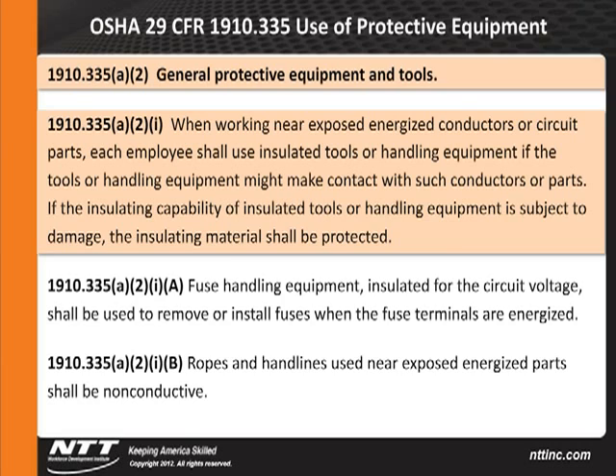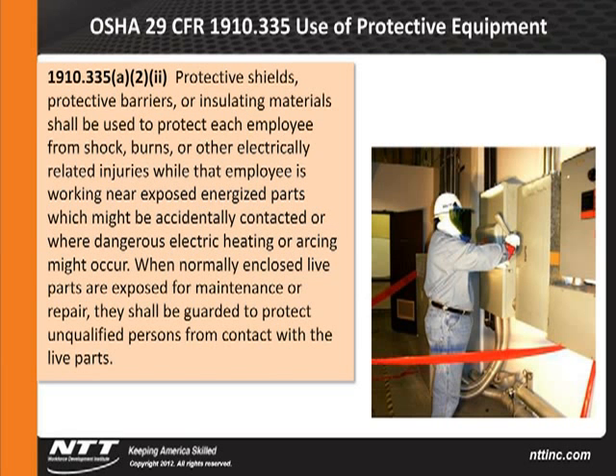And finally, protective shields, protective barriers, or insulating material shall be used to protect each employee from shock, burns, or other electrical-related injuries while that employee is working near exposed energized parts which might be accidentally contacted. And, of course, we're dealing with an exposed part or where dangerous electric heating or arcing might occur. And here's where we get into it. You see a picture up here. Is there a potential hazard there? Absolutely. Simply switching there could create a hazard. Something goes wrong in there, we've got an enclosure door, and it's possible for that door to come out.